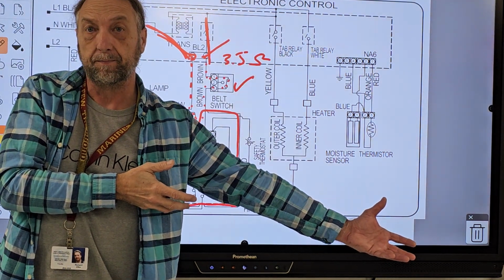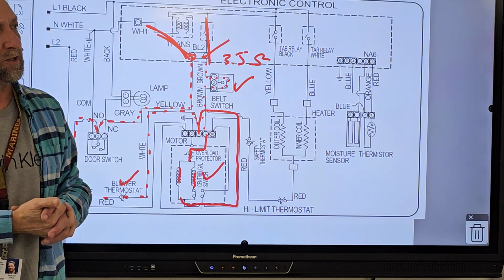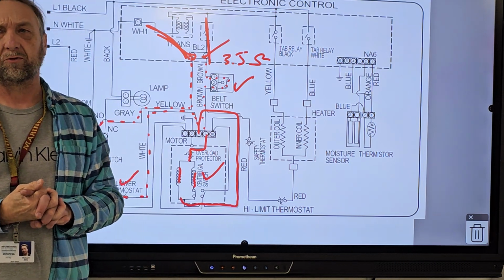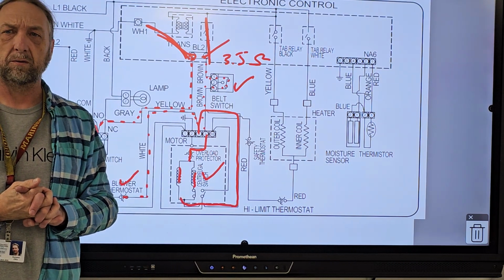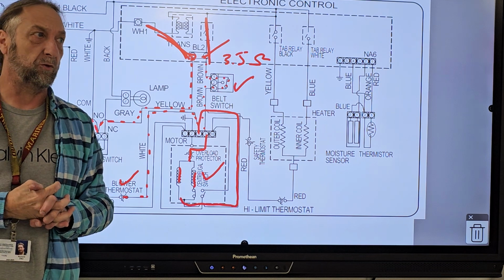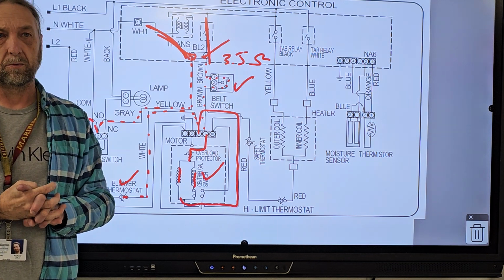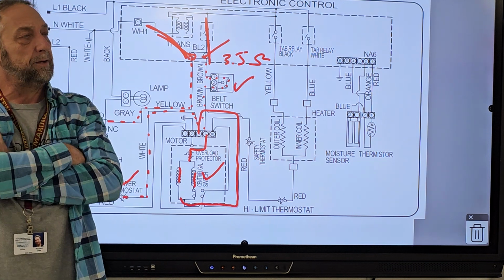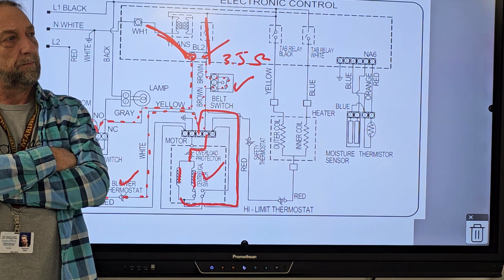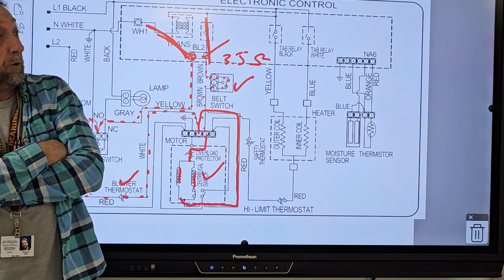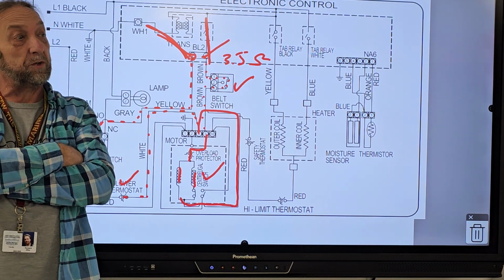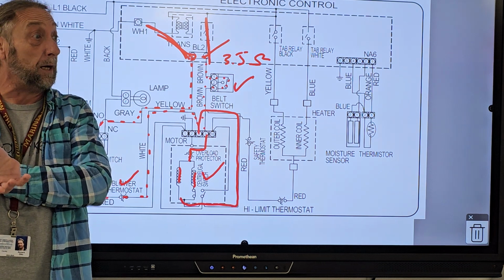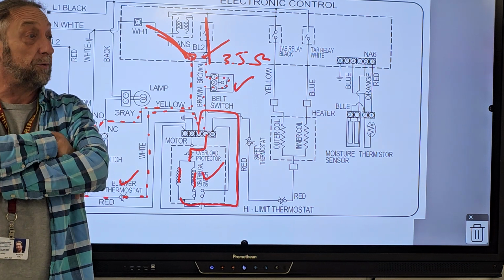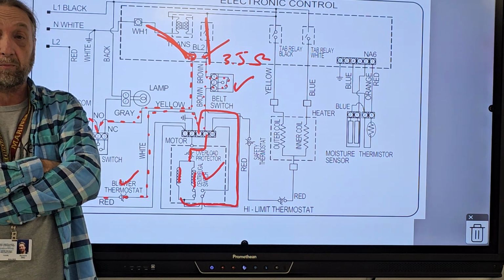Okay? Now, the technician said I have 107 volts. Is that good? No. Might be a little too low for the motor. So now what did I tell my technician? Check the power from the wall. Well, we have power to the wall, and try and tell the customer it's a power problem when the board's lighting up. It's very difficult to convince the customer that that's the problem.